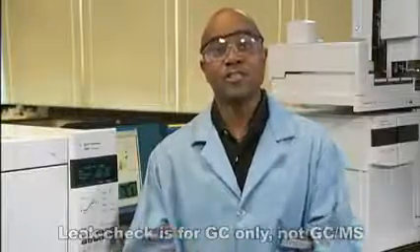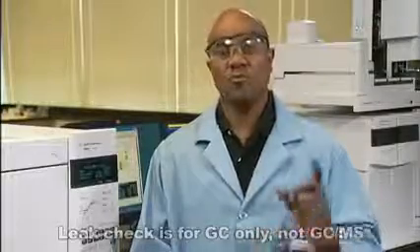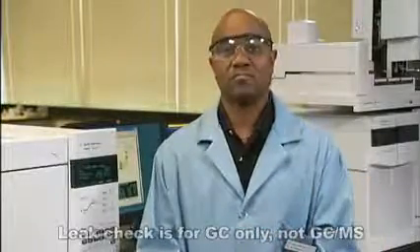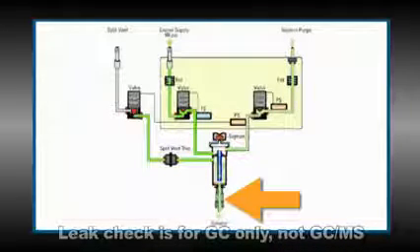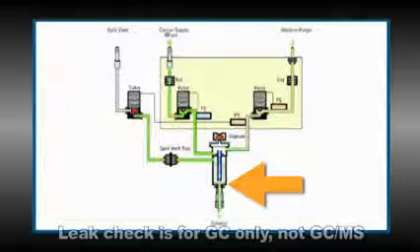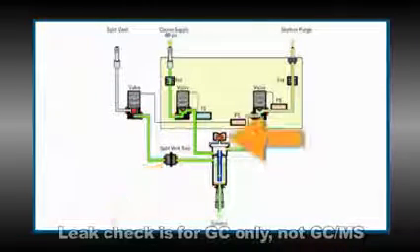Also, it uses the GC flow sensor to measure the leaks, and you get feedback when you find and fix the leak. Here's a sketch of the leaks it should help you find. It finds leaks at the inlet column fitting, the gold seal, the split vent trap housing and the vent line, the septum, and the septum nut.